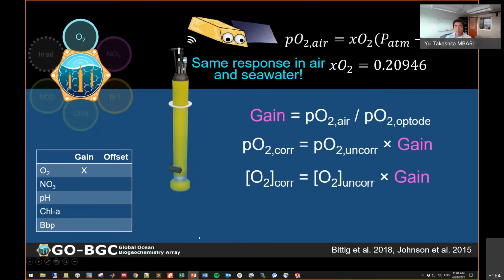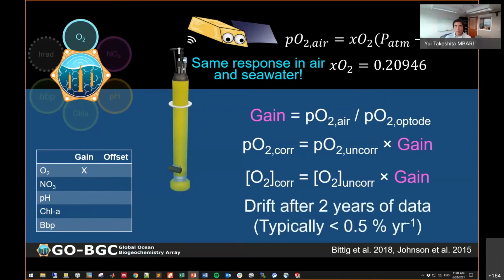Oxygen sensors tend to be very stable over time, but they do exhibit some drift over multiple years. Since the signal is really small, we currently only correct for drift if 2 years of data is available, and only if the drift is significant. Typically these sensors drift by less than 0.5% per year. But if the float lives for 5-6 years, then that can add up to be a pretty significant source of bias. So we will correct for that.